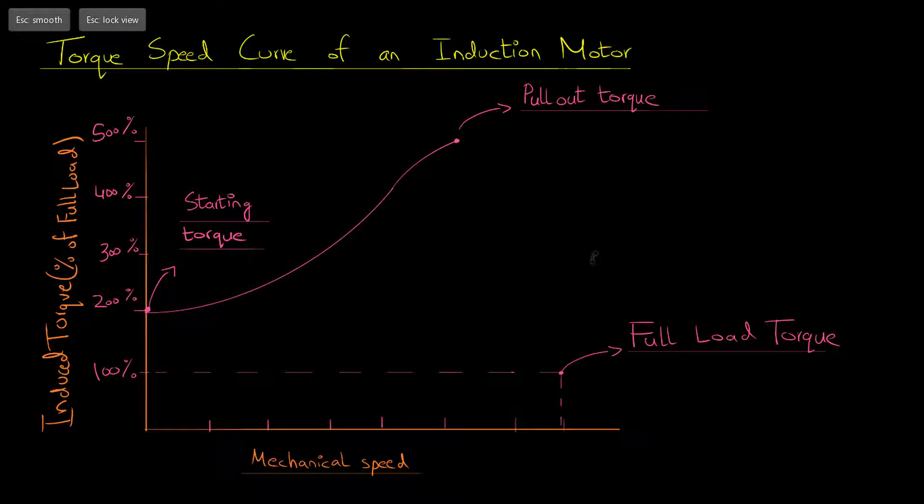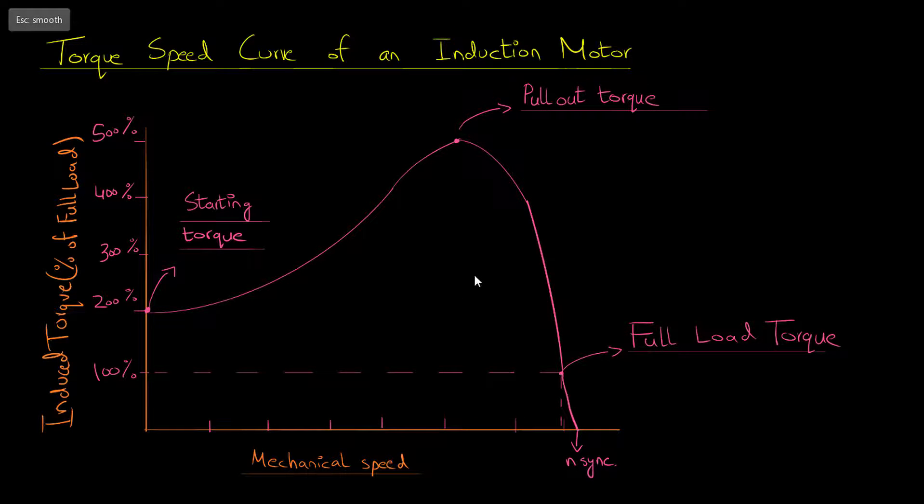The pullout torque is the value of torque that theoretically cannot be exceeded by the motor, and the pullout torque is around 2-3 times the full load torque. Then the curve dips down sharply and reaches zero at the synchronous speed because the torque developed at the synchronous speed is zero.